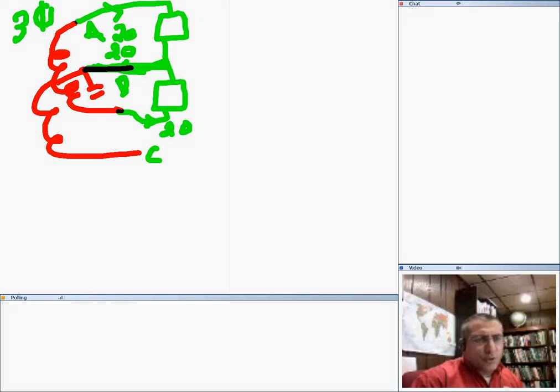And an uninsulated conductor in type SE cable is permitted to be used as, if you have an SE cable, my friend, and a bare conductor with it, the only place you can use that bare conductor is as an equipment grounding conductor. There's a lot of you who scored low on this one.